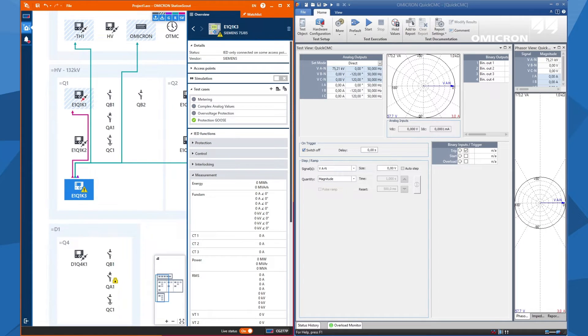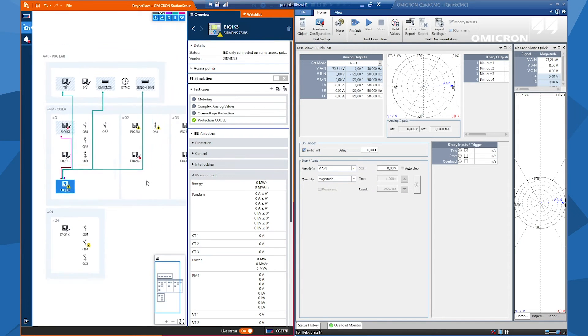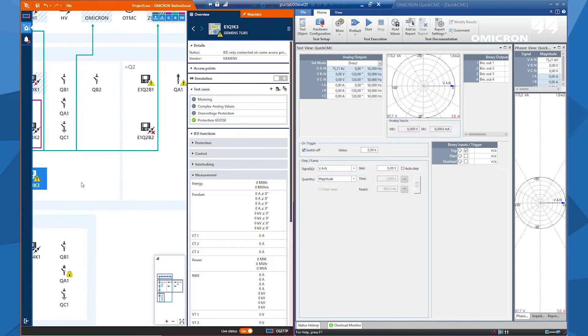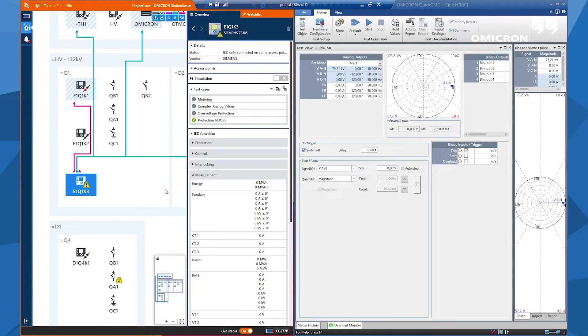Now I want to perform a point-to-point testing demonstration with StationScout. Here I have a small system where we will inject some values with CMC and observe these values. We will also change some positions and observe this in StationScout as we create a test case. Here I have an IED and I will create a test case for metering values.